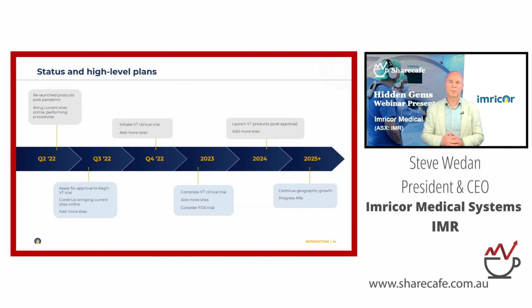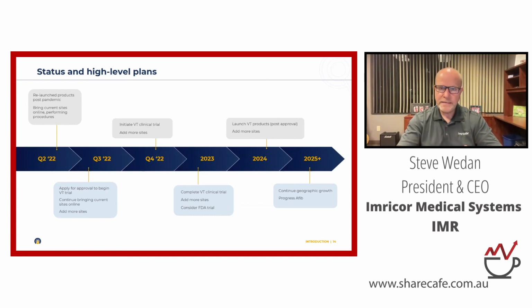And so the FDA approval is obviously something looking forward for the company. Can you talk us through that process and timing? You bet. So you start with this IDE that I mentioned. And once we have an IDE approved, then we have shared with the FDA all of our safety data and a clinical trial design. Then we execute that clinical trial. It gets reviewed, and FDA approval hopefully follows shortly thereafter. But it can be a couple of years of a process. That's why when we get our IDE approved, which we believe we'll have by the end of this year, we're going to take an assessment of whether it makes sense for us to drive forward with FDA approval right now, knowing that we wouldn't get approval for a couple of years anyway, or let European revenue ramp up so that we can self-fund that trial.